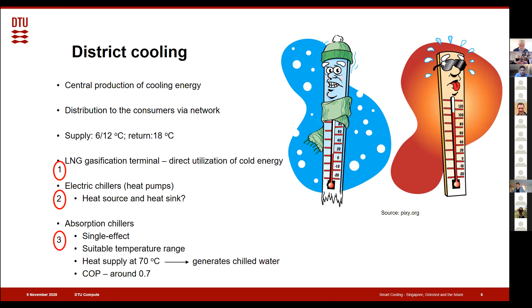In Singapore, one good source of direct cooling is actually a liquefied natural gas gasification terminal that releases approximately 0.23 kilowatt hours of cooling per kilogram of liquefied natural gas that is regasified in the terminal. The second and the third option are electric chillers and absorption chillers. The electric chillers are the usual cooling devices that are used all over the world, while absorption chillers are very interesting because they can use actually a heat source at approximately 70 degrees or above to produce chilled water. Their coefficient of performance is usually around 0.7.